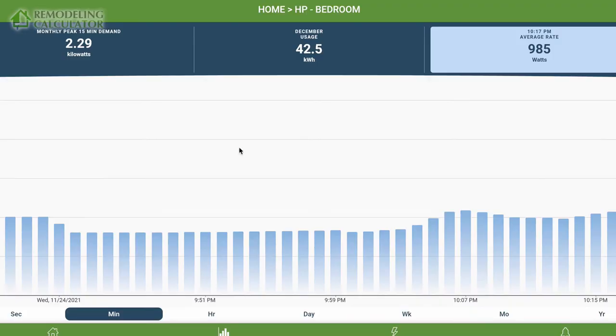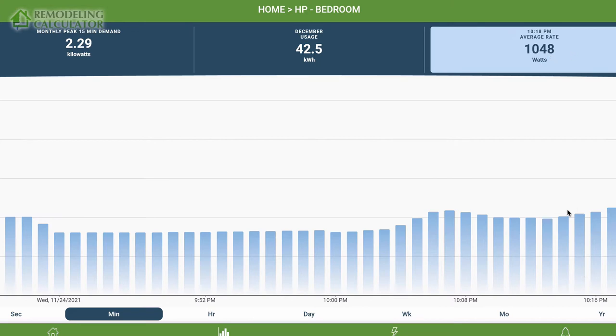As a quick sidetrack, this is an Emporia monitoring system that I use to monitor my heat pumps. I use air source heat pumps or mini-splits. Right now it's using 1,000 watts to heat a 600 square foot space — it's about 30 degrees Fahrenheit outside. That's equivalent to a medium-sized space heater you plug into the wall, maxed at 1,500 watts. I'm using 33% less energy to heat a 600 square foot space, whereas a space heater can only do about 150 square feet.